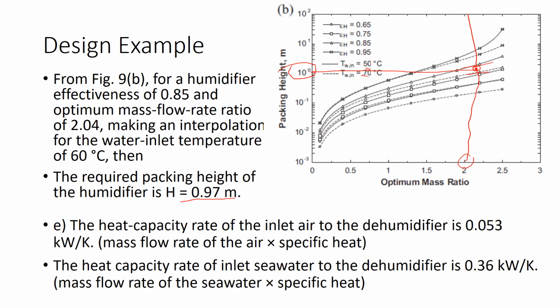Next is to size the dehumidifier, and to do that, we are going to calculate the heat capacity rate of the two fluids in the dehumidifier. In the dehumidifier, we have air coming in and we have water coming in. The heat capacity rate is nothing but m dot into Cp. So we calculate mass flow rate of the seawater into Cp of the water and mass flow rate of the air into Cp of the air. And then we compare these two values. So this is the heat capacity rate for the air. This is the heat capacity rate for the water. So the lower one of them is the air.